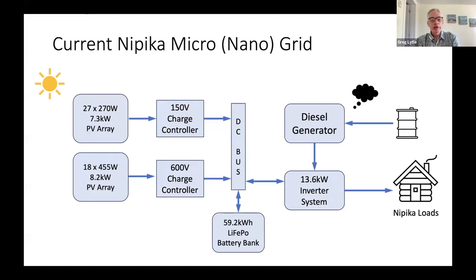So here's a schematic of our current system. We've got now two reasonable sized PV arrays feeding into charge controllers. We've got a new lithium iron phosphate battery bank, and we still have our existing diesel generator, which is used for backup or when there isn't sufficient solar to charge our batteries. And we've got new inverters supplying our loads.